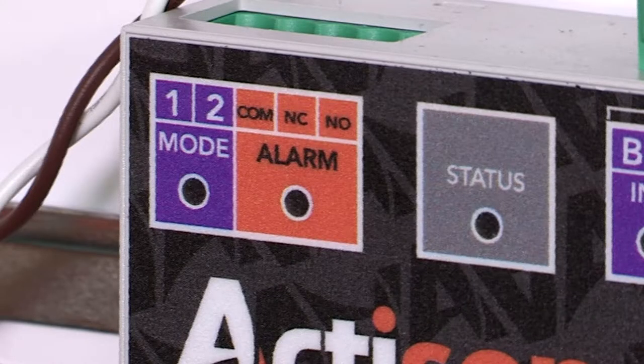an alarm output. As ground loop damage is the number one cause for instrument failure in NMEA 0183 networks, every port on the PRO-MUX-1 is electrically isolated to prevent ground loop damage. This means that the PRO-MUX-1 has reliability built in so you can set it and forget it.